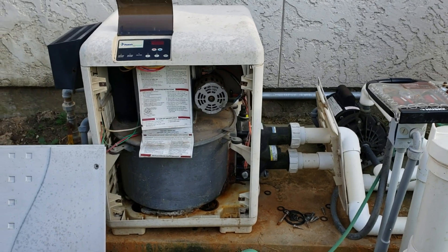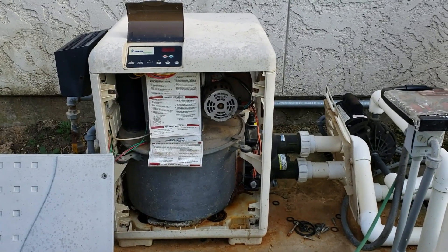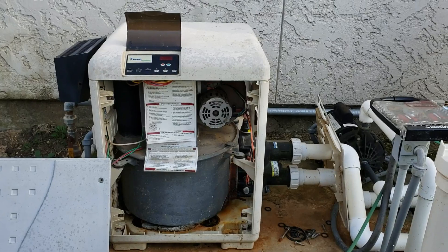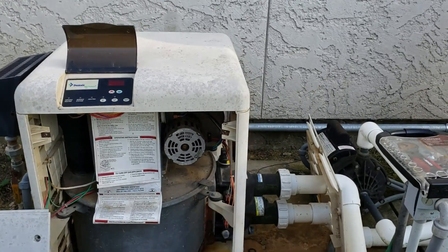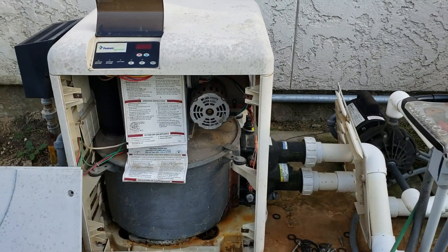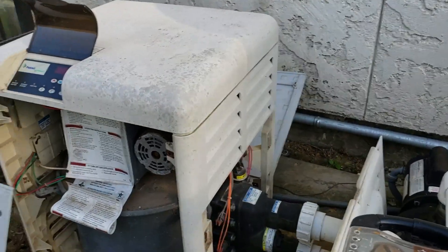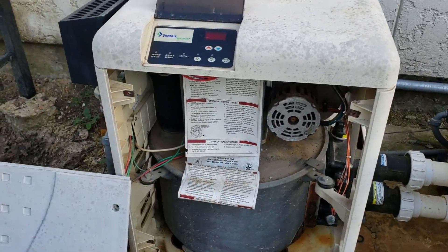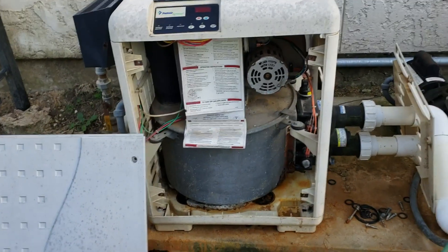I've got a Pentair Master Temp 400 and the tub is full of water as you can see from a previous video. I've got a leaking heat exchanger coils where the manifold mates to the side of the combustion chamber. So I'm going to take off the manifold, break the seal, take things apart, and replace the coils. They just came in today.